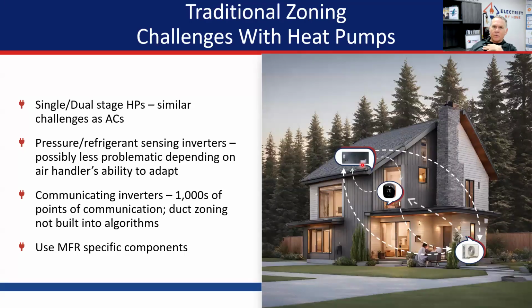So pressure and refrigerant sensing inverters are probably less problematic. So like your Bosches and GEs and some of the AC Pro stuff and some of the Bryant stuff and some of the Midea, some of those units work off of temperature control and not communication. Basically if we're blowing air across the coil and we've got a full amount of airflow and a predictable coil temperature, because I've got low static pressure and the thing is running like it's supposed to, that unit can bounce all the way up to high speed if it needs to. And as the coil gets colder, which means the house is getting colder if I've got perfect airflow, that unit will slow down.